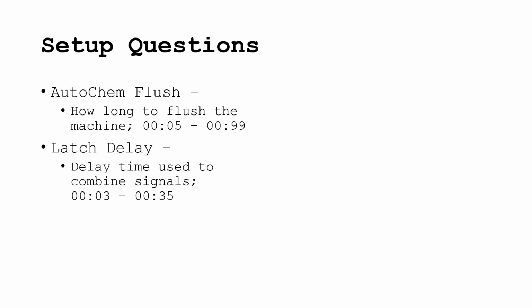Latch delay. The delay time is used to combine signals from machines that cannot turn on all the chemical signals at the same time. For machines that can turn on all signals at the same time or there is not a delay in between the signals, the latch delay should be set to 3 seconds. For machines such as a Braun or a Milnor EP+, the time should be set from 20 to 30 seconds. Refer to the schematic for more information. Recommended range 3 to 35 seconds.